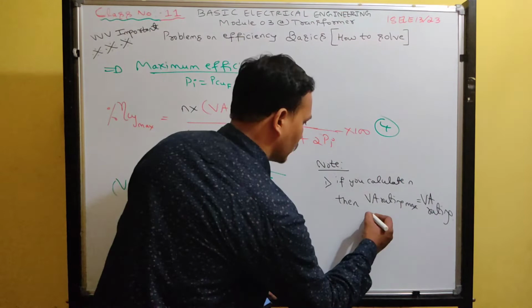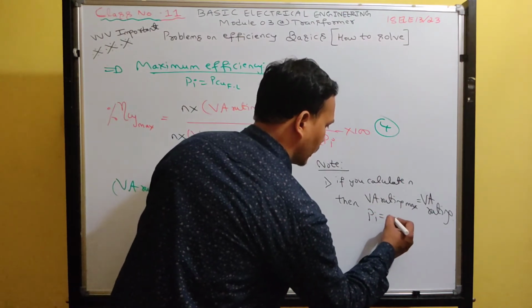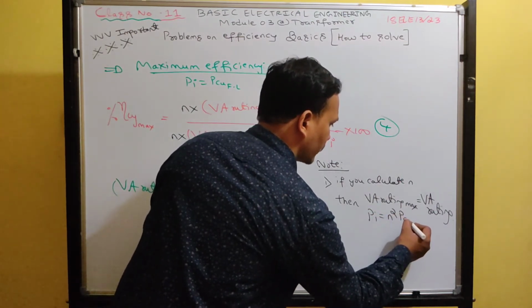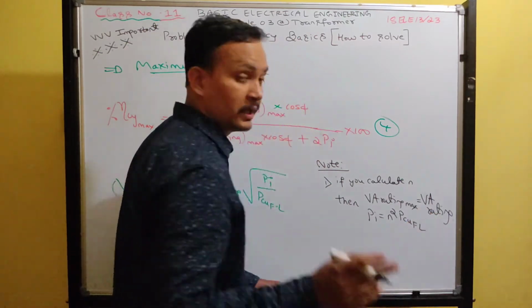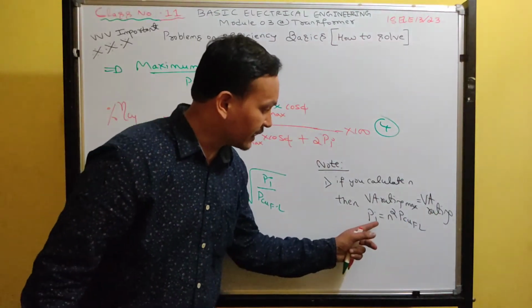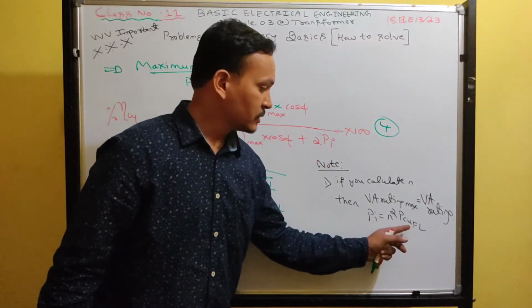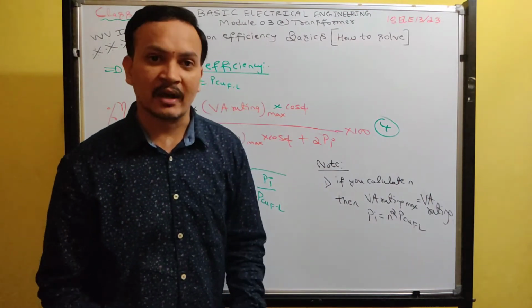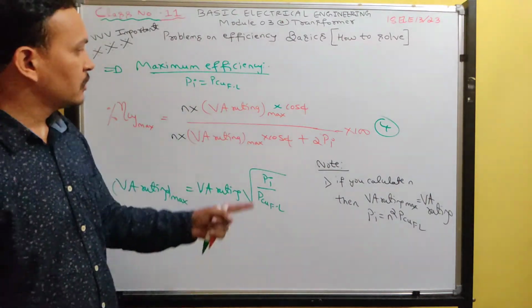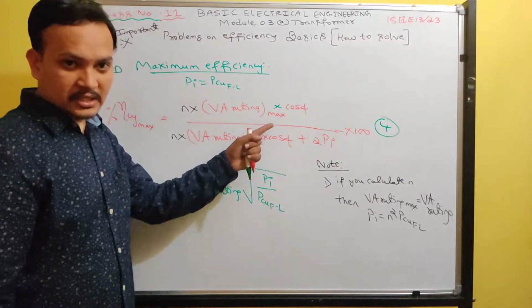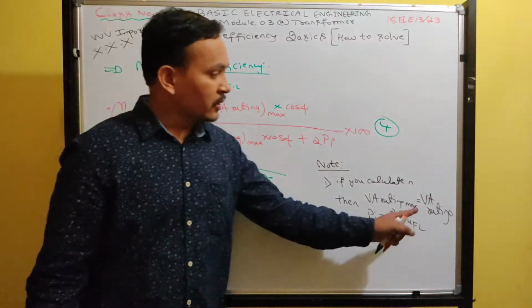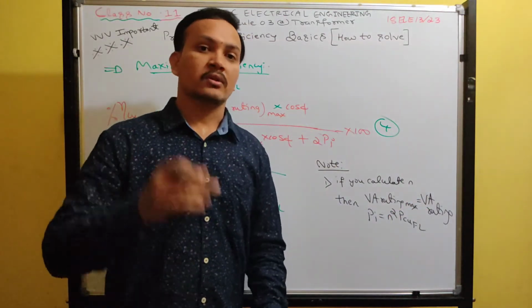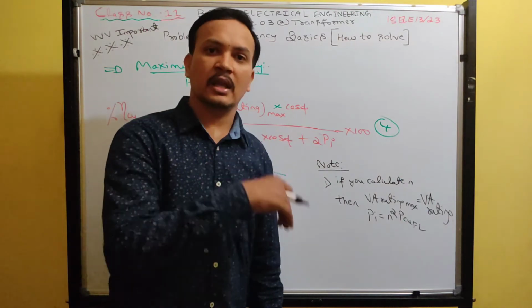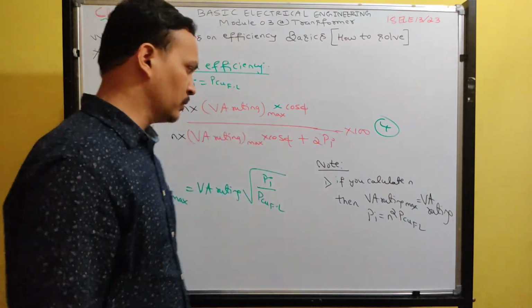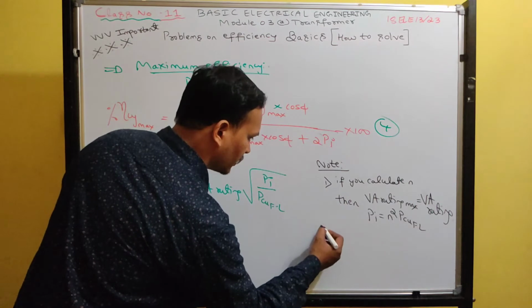So how to solve that? See, by using this formula: Pi is equal to N square PCU full load. In the problem, they will specify iron loss and copper loss, so from that you can easily find the N value. If you calculate N, then the volt ampere rating maximum is nothing but the volt ampere rating. In the question they will give 50 kVA. Take that kVA only. Okay. So this is one note. Next, the second note.